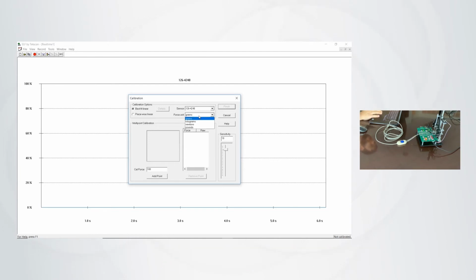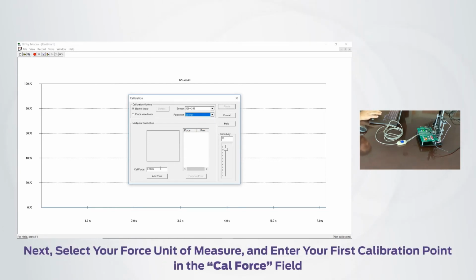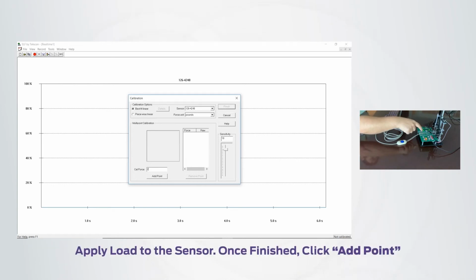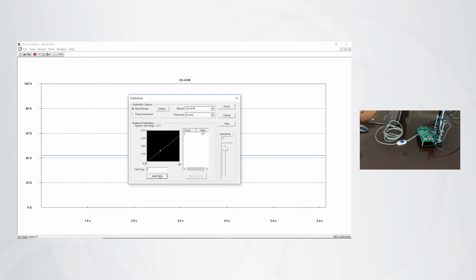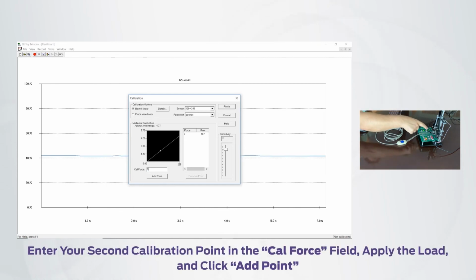So the first thing I'll do is adjust my units to pounds. Input my first calibration force, which is 2. And we'll apply 2 pounds to our sensor. So now we've got about 2 pounds on the sensor, and we will capture this calibration point. And now we will capture our second calibration point of 5 pounds. So we'll input it there, and then we'll change our load to 5 pounds. And there's our 5-pound load, and we'll go ahead and add it.